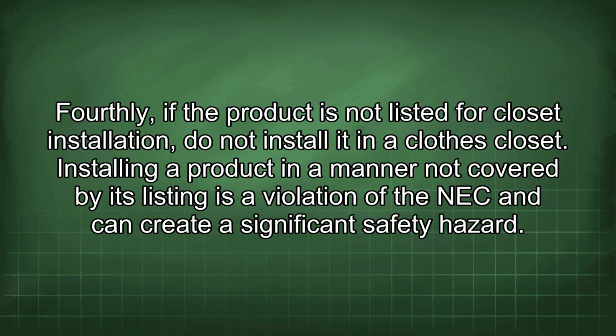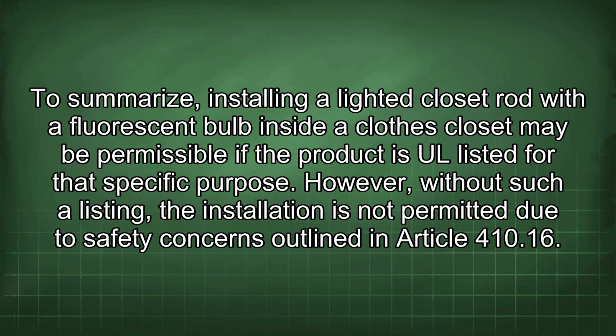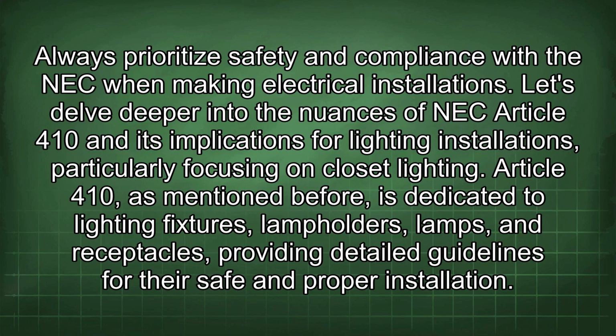To summarize, installing a lighted closet rod with a fluorescent bulb inside a clothes closet may be permissible if the product is UL listed for that specific purpose. However, without such a listing, the installation is not permitted due to safety concerns outlined in Article 410.16. Always prioritize safety and compliance with the NEC when making electrical installations.